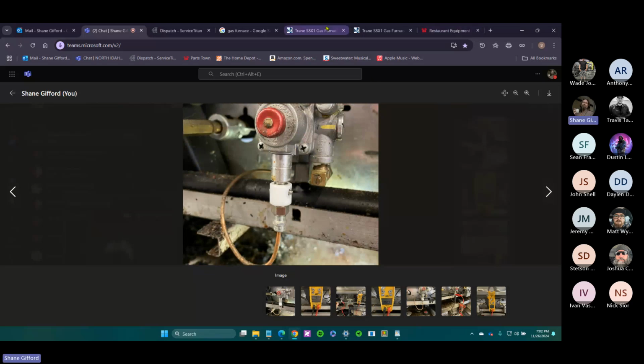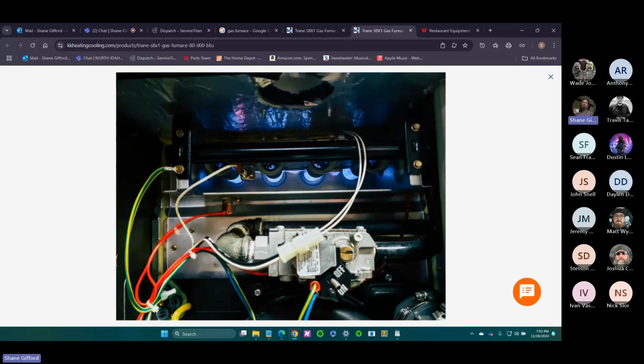The same thing applies here. So that flame sensor is the same thing. You can call it an electrode, or, you know, no, an electrode creates spark, but that's your flame sensor. That's your thermocouple or your thermopile. How you would test it in this scenario is take the wire off, put your black lead through there and let it just bite into itself. Take your red lead and hold it onto the tip or the male spade. And then when it goes to fire, not only have you completed the circuit, but it'll keep running, and then you can read your millivolts or milliamps.